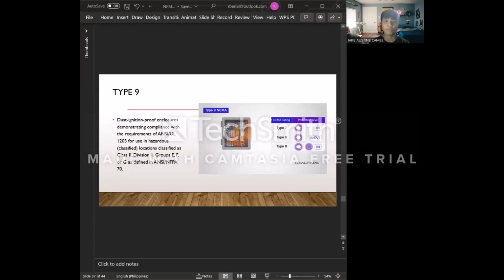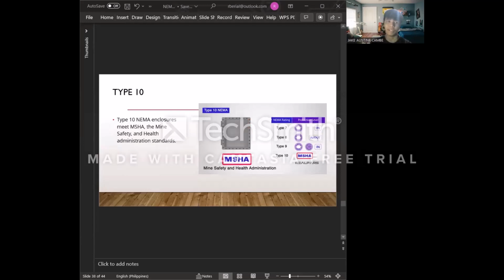So type 9 NEMA enclosures are ignition proof. It demonstrates compliance with the requirements of ANSI/UL 1203 for use in hazardous classified locations, classified as Class 2, Division 1, Groups E, F, or G, and as defined in ANSI/NFPA 70. So type 9 NEMA enclosures are ignition proof and intended for indoor use only in hazardous locations. So next is the type 10 NEMA rated enclosure.